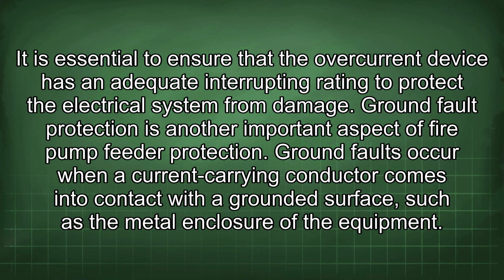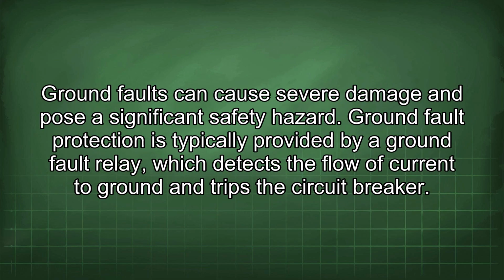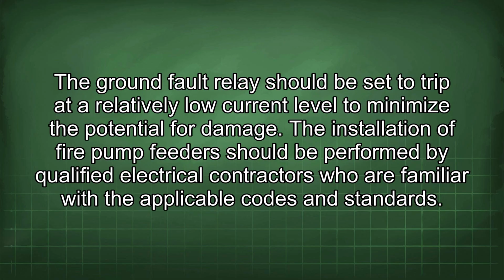Ground fault protection is another important aspect of fire pump feeder protection. Ground faults occur when a current-carrying conductor comes into contact with a grounded surface such as the metal enclosure of the equipment. Ground faults can cause severe damage and pose a significant safety hazard. Ground fault protection is typically provided by a ground fault relay which detects the flow of current to ground and trips the circuit breaker. The ground fault relay should be set to trip at a relatively low current level to minimize the potential for damage.